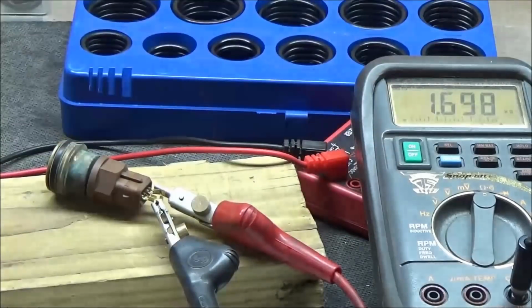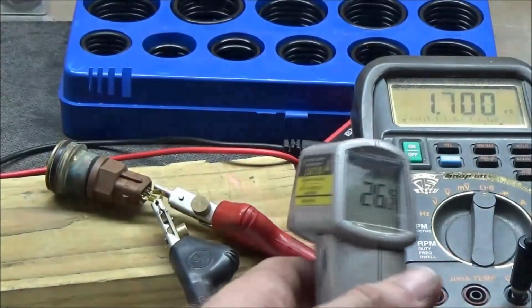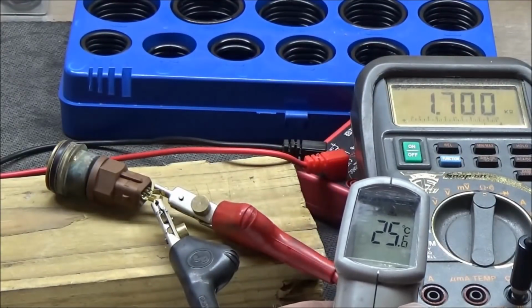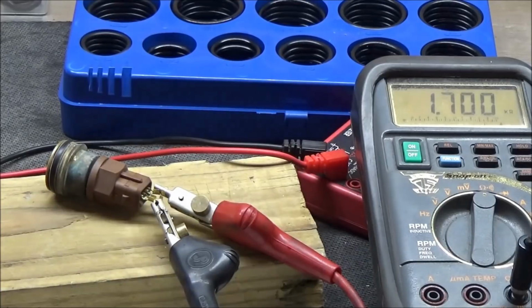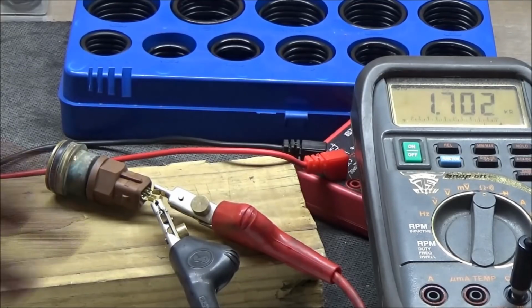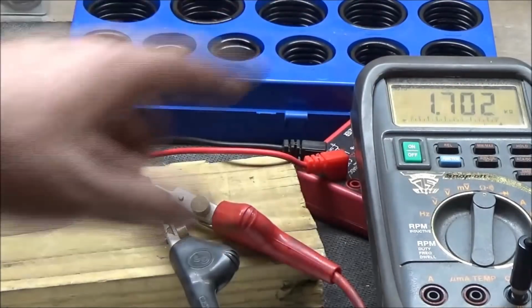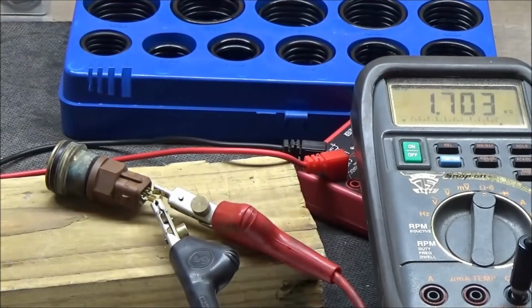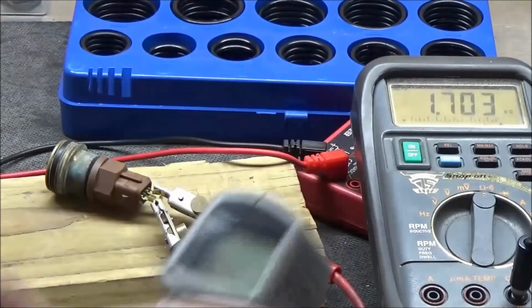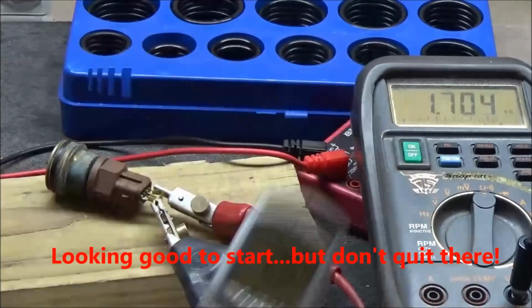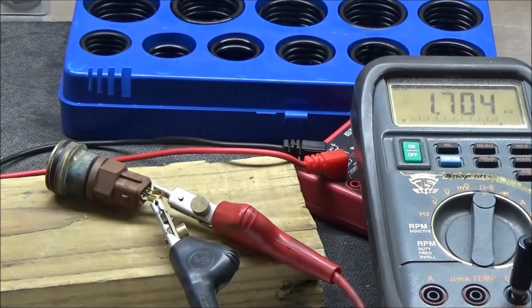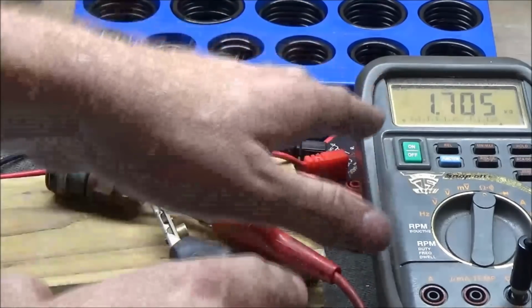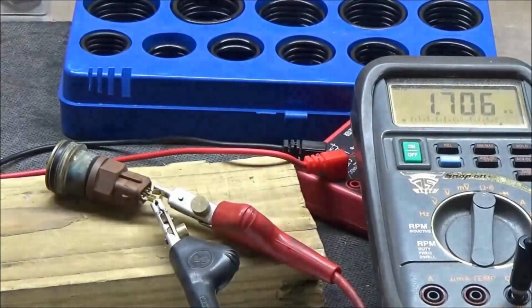I'm getting 1.698 thousand ohms - that's K for kilo-ohms - at 26 degrees. Important factor: this chart goes the other direction. What you'll notice is the resistance got less and less as the temperature went up, so that number should be smaller. The last spec in the manual is 2.35 to 2.65 kilo-ohms at 20 degrees. So if you do some basic math, you can see the sensor is trending in the right direction for resistance. But I'm going to take it a step further.